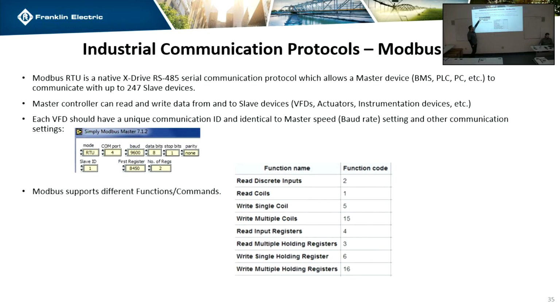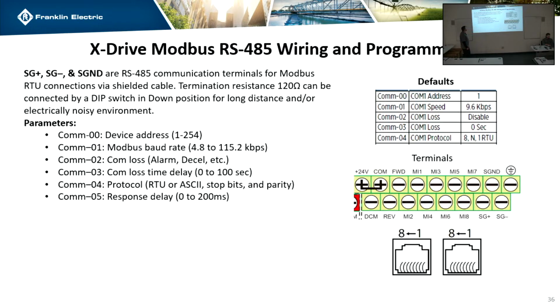I have a simply Modbus set up on my computer at my office, so I can go through and do different tests. If someone says it's not working, or I can't read this, or I don't understand what it's telling me, I can hook it up and walk through it. But for the most part, like you guys just said, we're not communication guys. Those guys are in their own world. We just need to make sure that the drive is able to communicate in a way that they can understand. And then these are the names and function codes, but we don't really need to go over it.